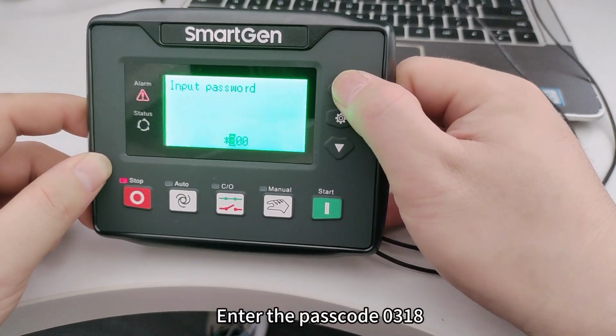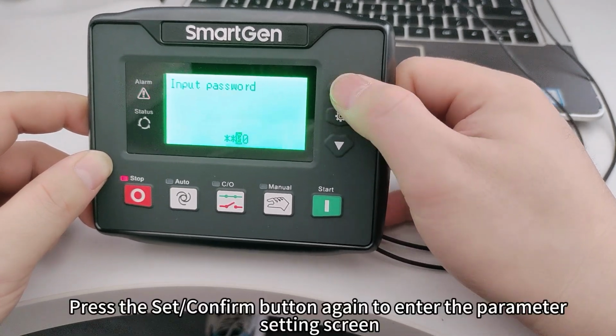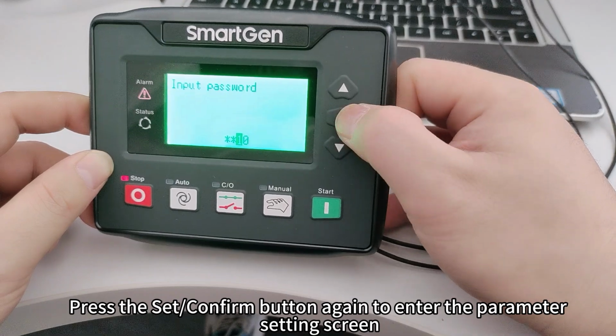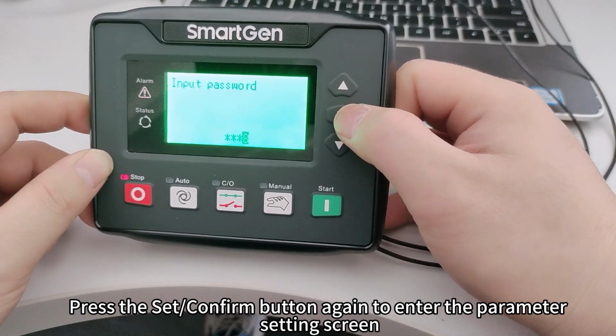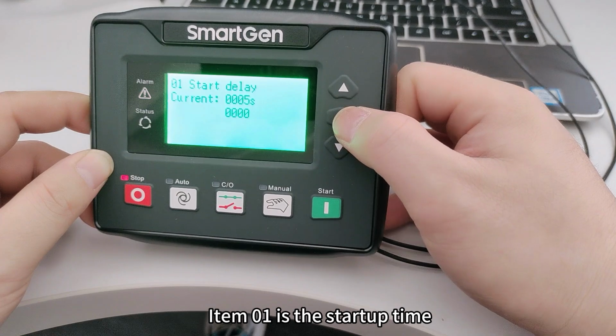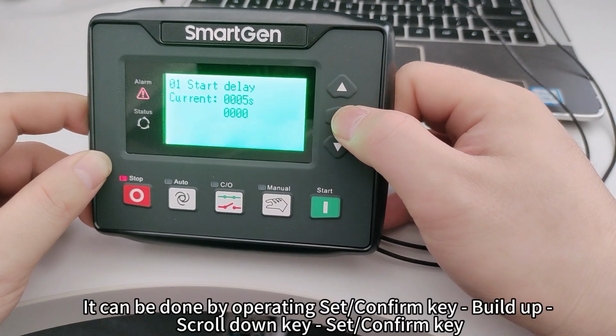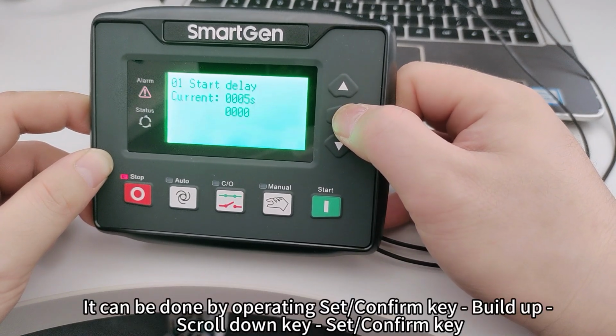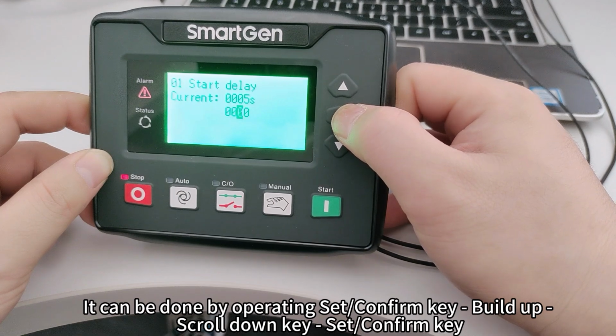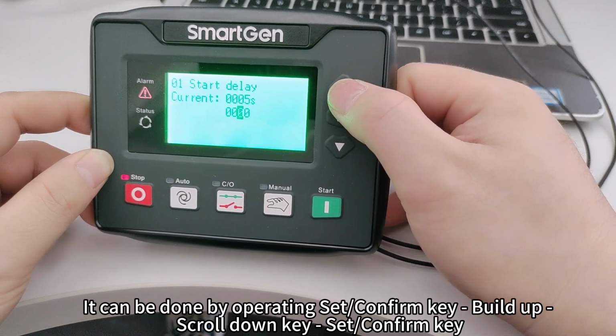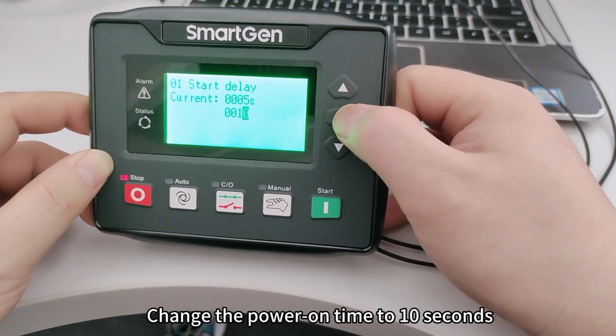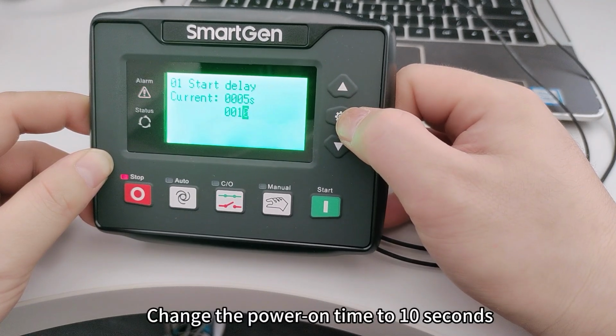Enter the passcode 0318. Press the Set Confirm button again to enter the parameter settings screen. Item 01 is the startup time. It can be changed by operating the Set Confirm key, the scroll down key, and the Set Confirm key again. Change the power on time to 10 seconds.